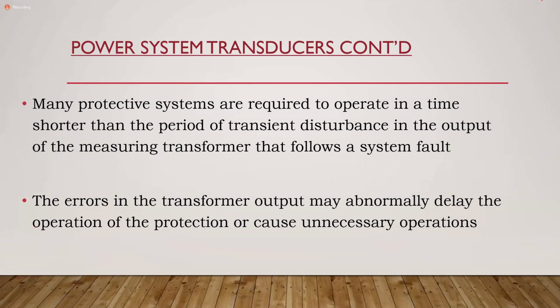Where are we here? Excuse me, sir. So, sorry, so the CT would have been the so-called measuring instrument that relays the information to a relay. I think I asked this. All right. The CT gives you a scaled replica. So the CT converts what is on the system to a value that is in a certain ratio, which comes to the relay. So in effect, it's not really measuring. It's converting what's on the system to a particular value.